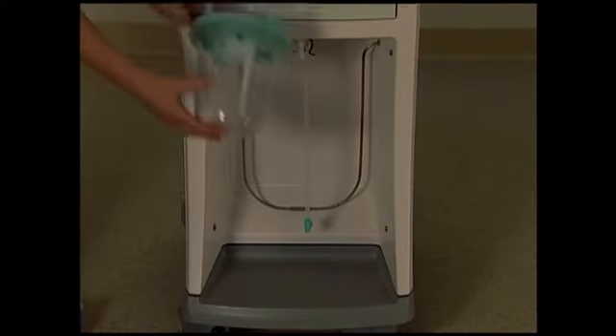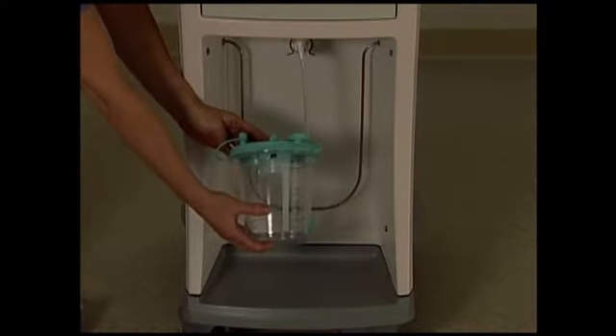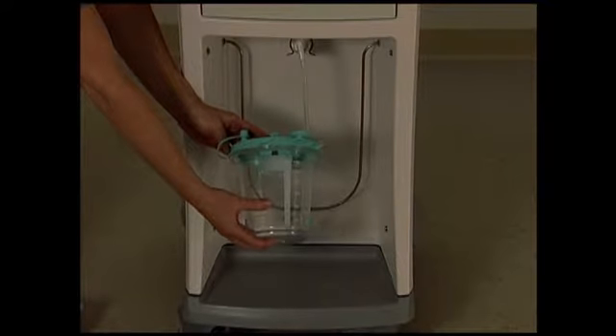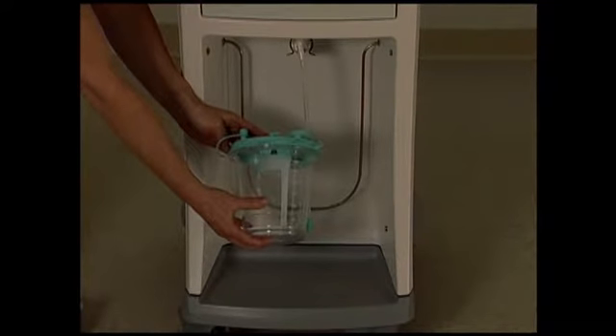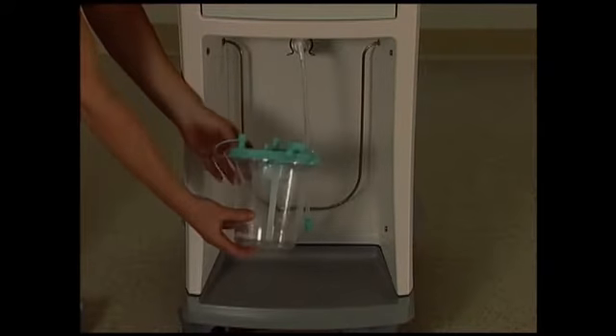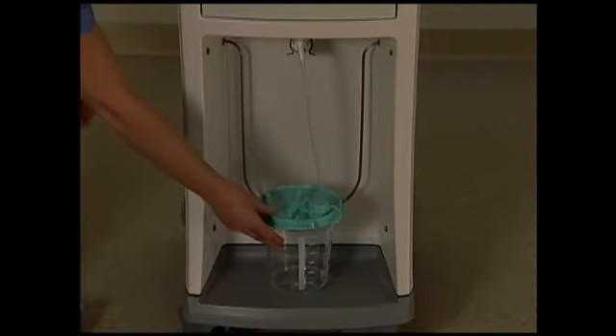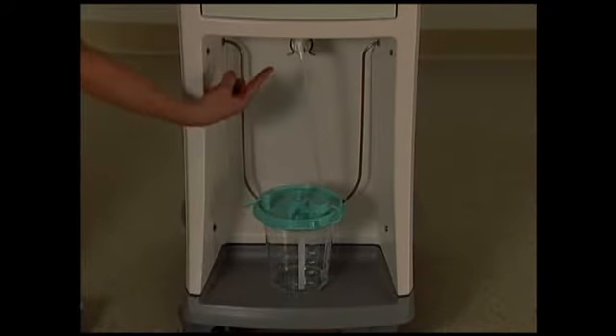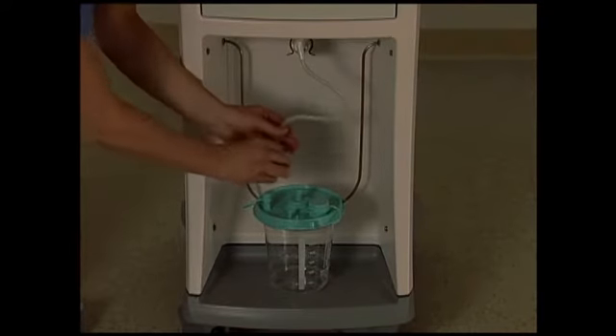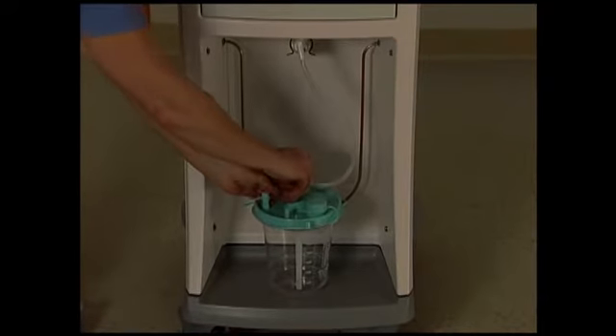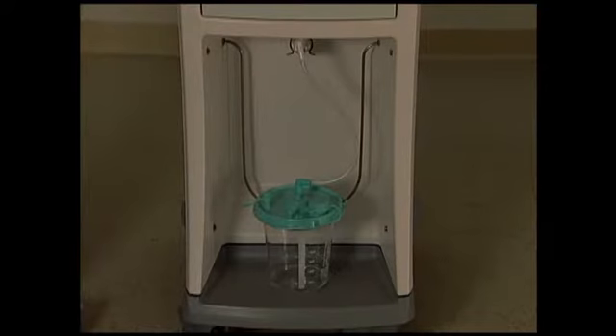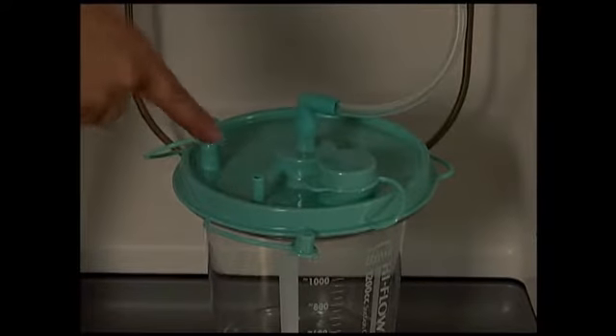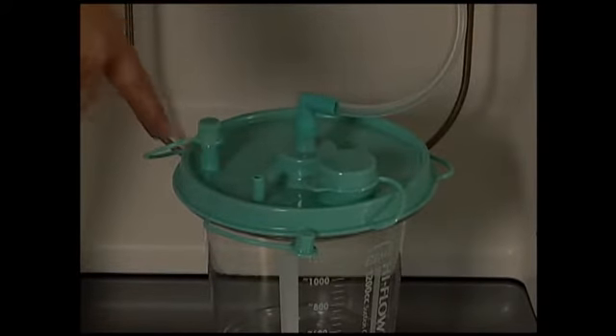It is suggested that a hard-sided waste collection canister be used when operating the CUSA NXT system. To set up the waste collection system, first place the canister into the base of the service module. Ensure that the contamination guard is installed to protect the vacuum pump in the service module. Connect the tubing from the contamination guard to the vacuum port on the canister. Note that the top of the canister has a patient port open. This is where the tubing from the handpiece will be connected.